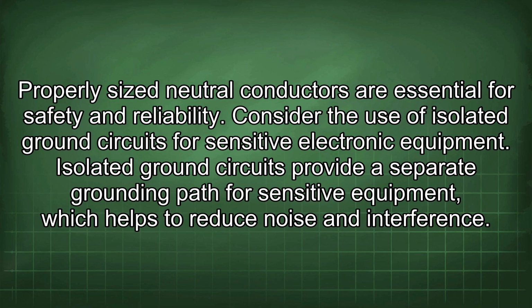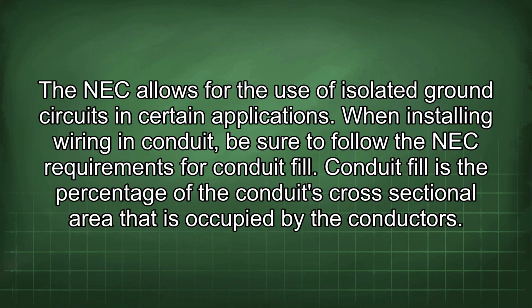Consider the use of isolated ground circuits for sensitive electronic equipment. Isolated ground circuits provide a separate grounding path for sensitive equipment, which helps to reduce noise and interference. The NEC allows for the use of isolated ground circuits in certain applications.